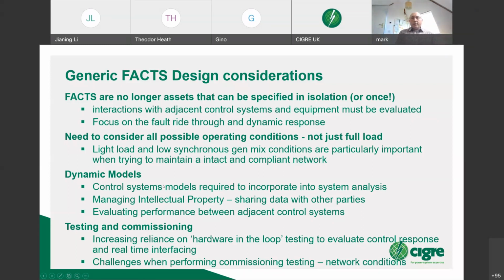A lot of the time, traditionally, people are always focused on full load. One of the bigger challenges at the minute is actually focusing on light load conditions, and particularly periods where you're going through a transition from one state to another. So what's the sensitivity of that control system, that asset, to those conditions, and being able to model that and understand what that means in the particular control system specifications you're looking at, which means you've got to spend a lot more time looking at your dynamic model.